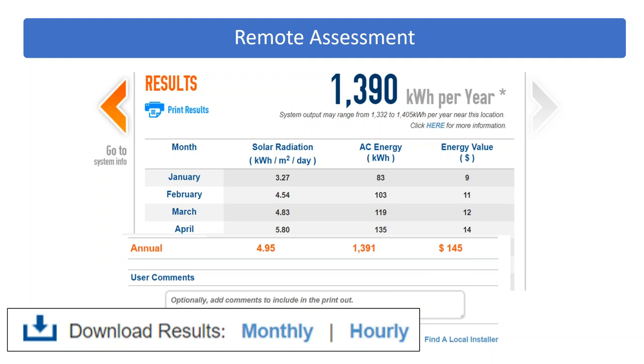If you take a solar array on a rooftop facing south and you rotate it to east or west, you're going to lose up to about 15% of the system production. You might think, well, isn't that a lot? And I guess it is, but you're also doubling the project size. So if you can achieve a 20% discount by doubling up on your project size, it might actually be more cost effective to do a larger array rather than a smaller array.